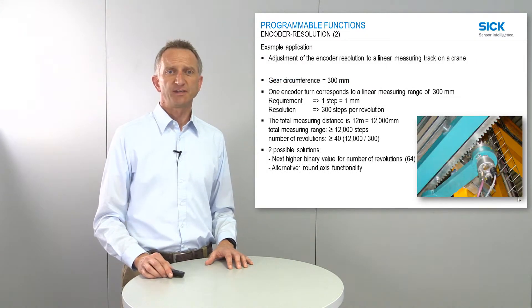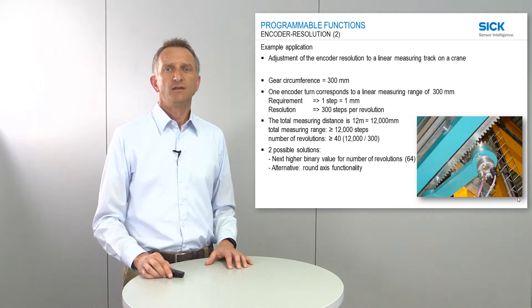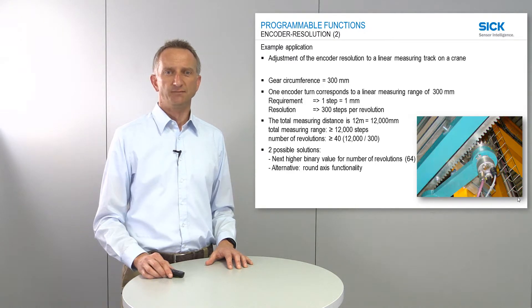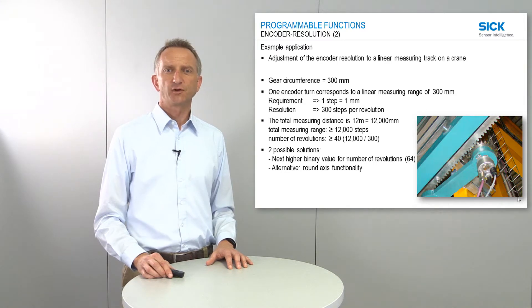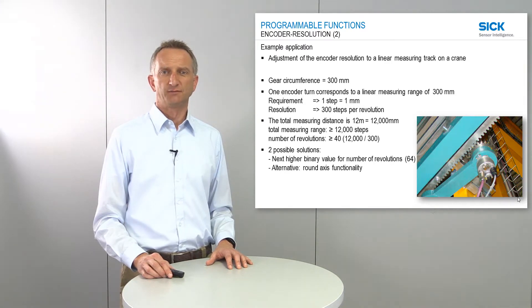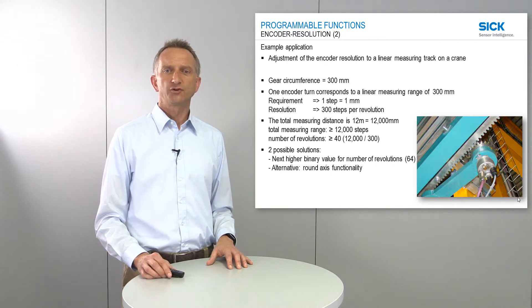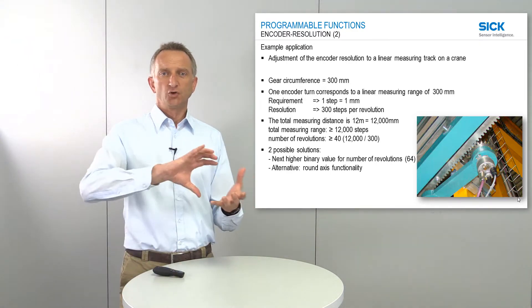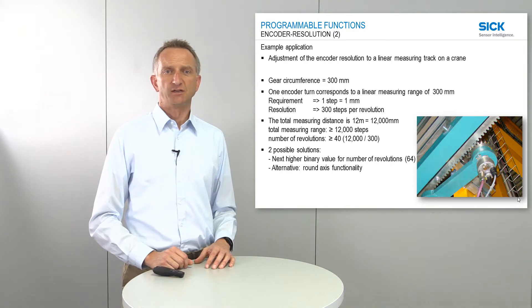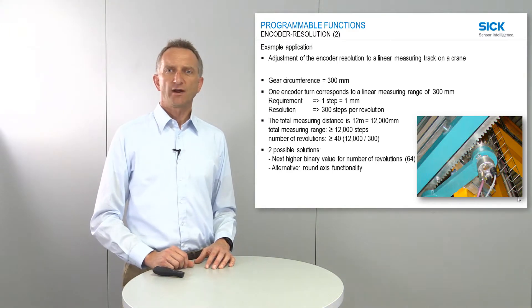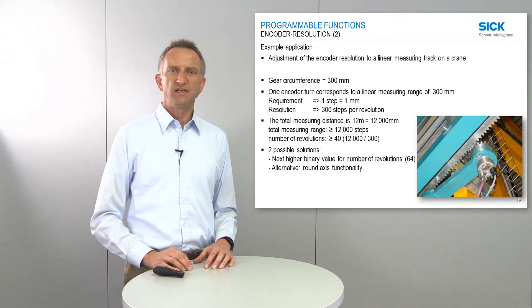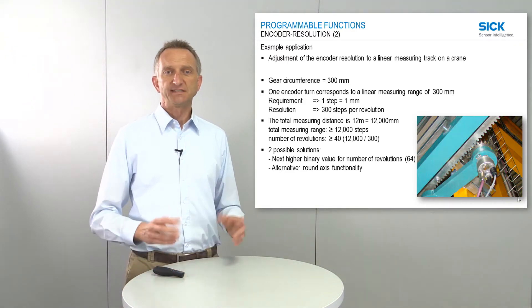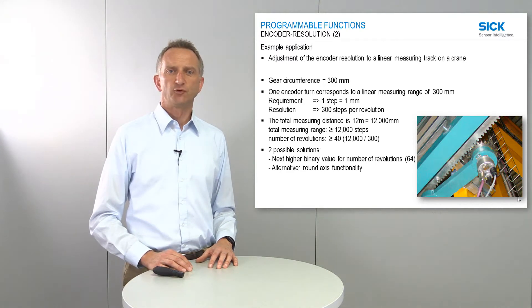Let's have a look at a first application example. Here we are looking at a linear measuring track on a crane. The encoder is assembled to a gear with a circumference of 300 mm, meaning one encoder turn corresponds to a linear measuring range of 300 mm. The requirement for this application is to have one step equaling 1 mm, which means we have 300 steps per revolution.